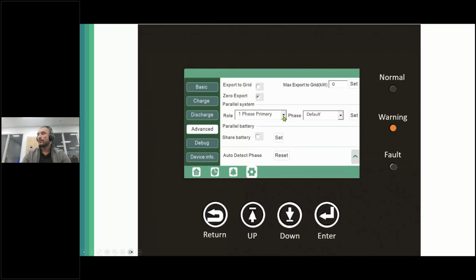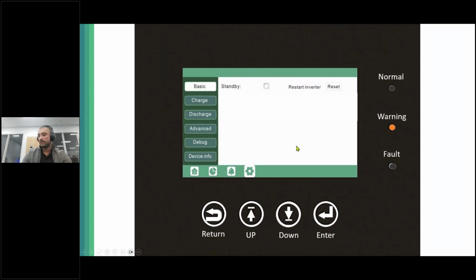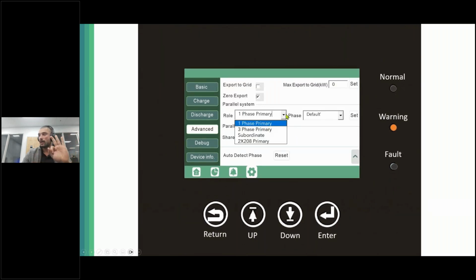For the subordinate - let's say you have three inverters as we spoke - I'm going to select the subordinate, whether it's single split phase or three phase. The second inverter is going to be subordinate. If it's three phase, I'm going to select the S phase. Then for the third inverter, I'll select subordinate again and the T phase. If it's not three phase, if it's single split phase, you can just keep it as default.